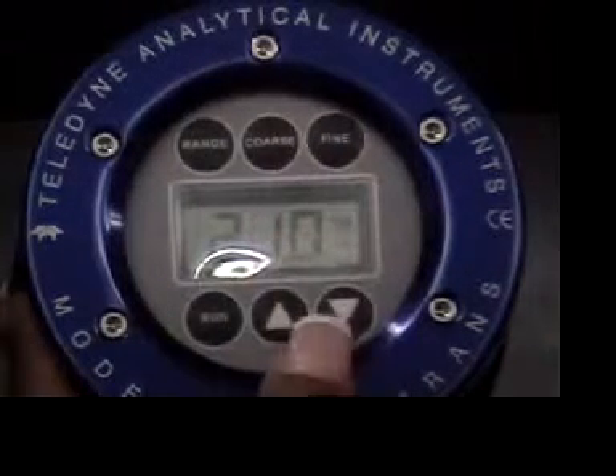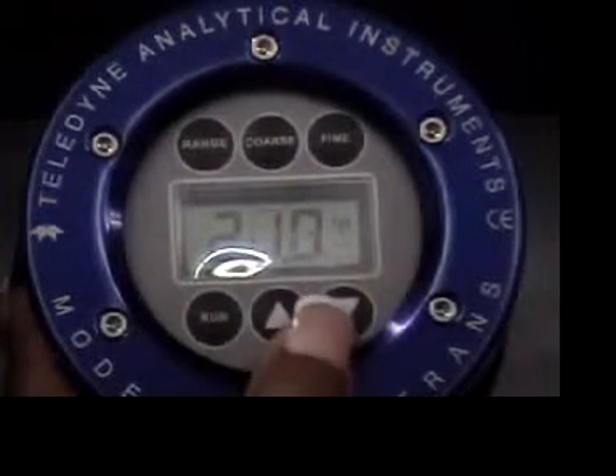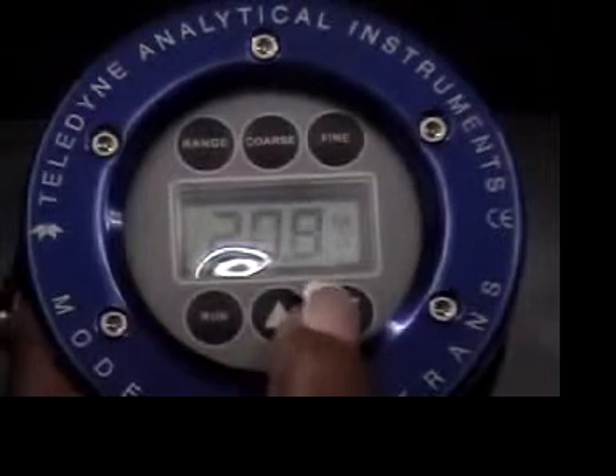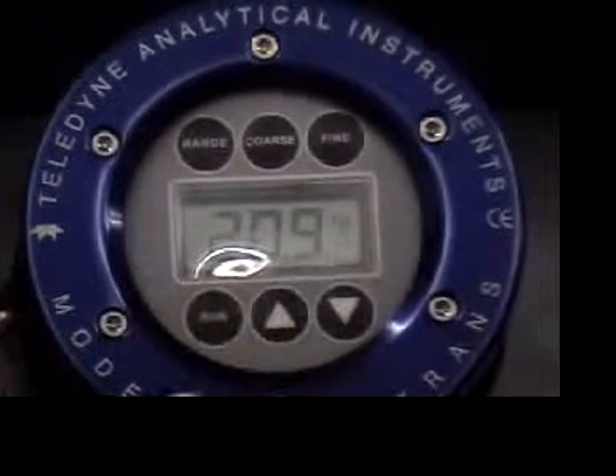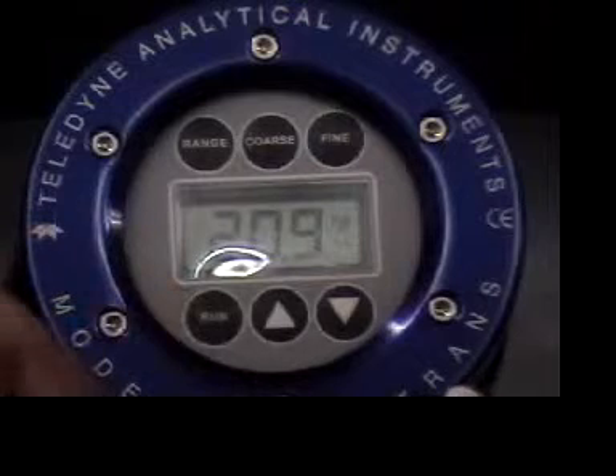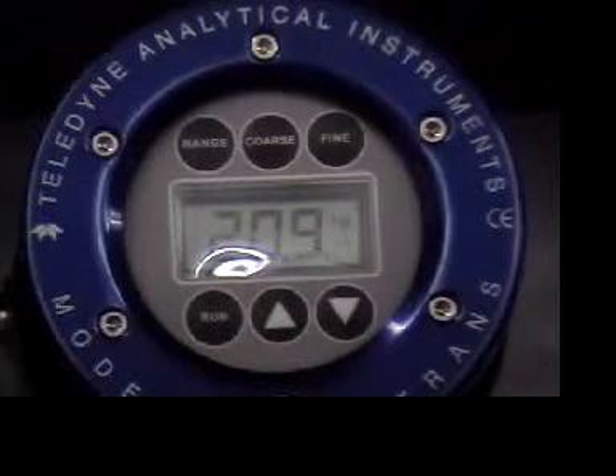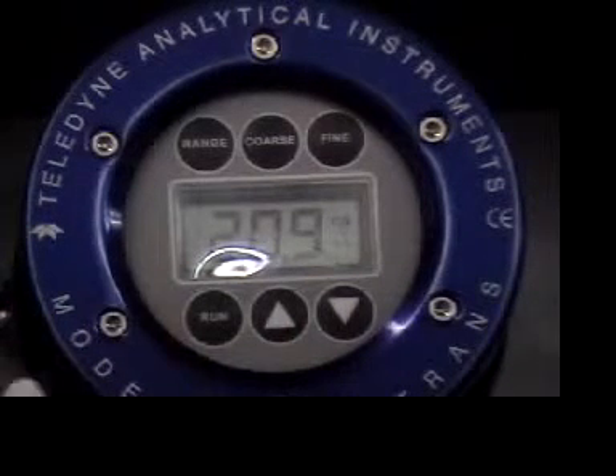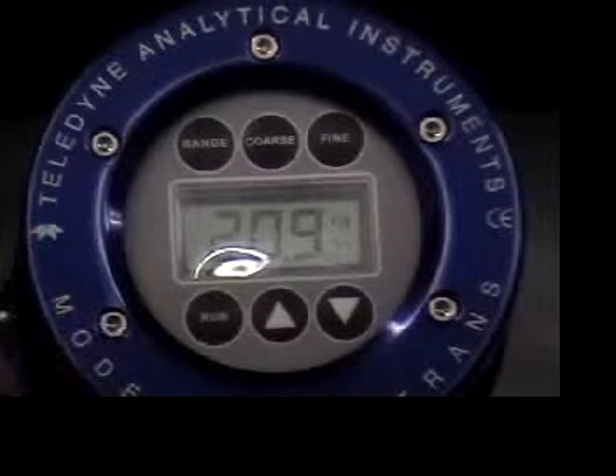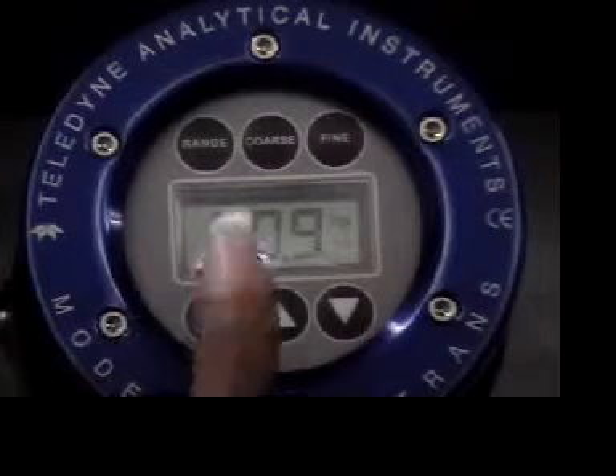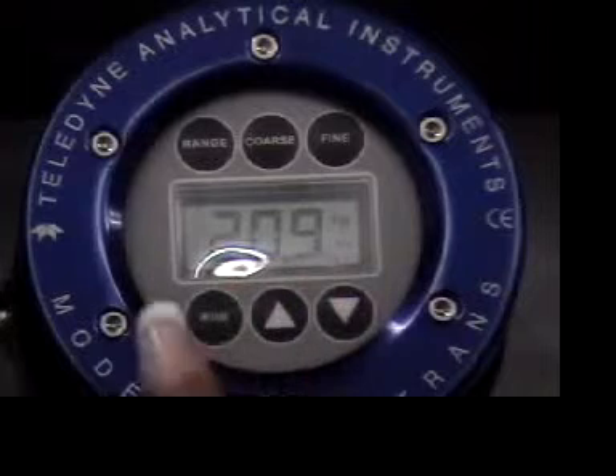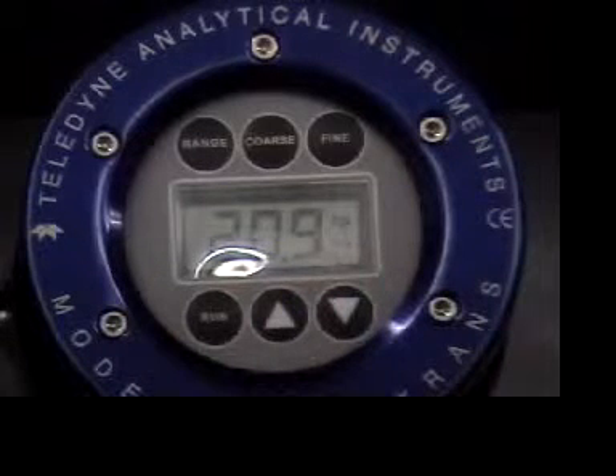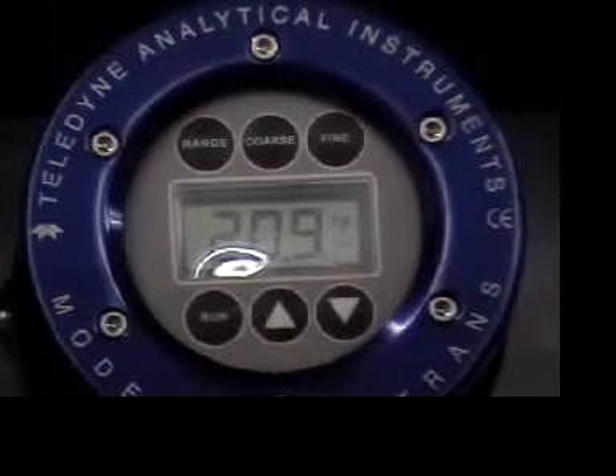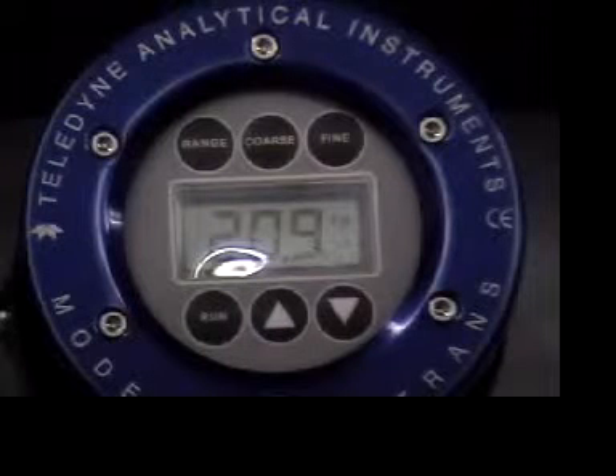If I need a closer adjustment, I can press the fine button, which allows me to make it just a little bit closer. Right now we're at 20.9, which is where I want to be for a 20.9 air calibration. If your span gas is something else, you would adjust for that. Once you've done the coarse and the fine, and made your adjustment for the cal value, whatever your span gas is, your calibration is complete.